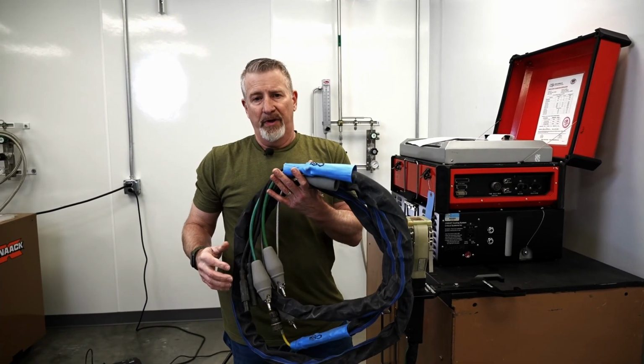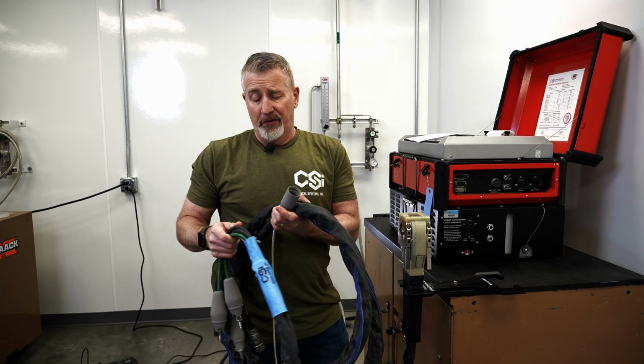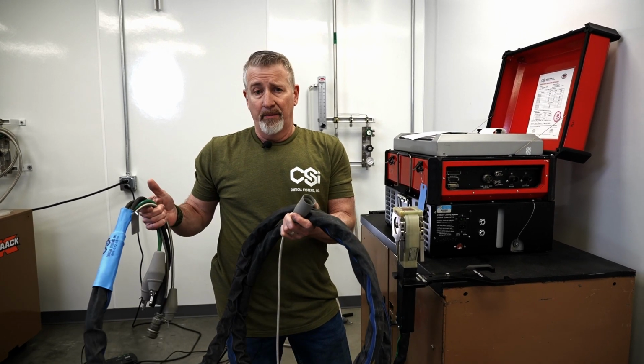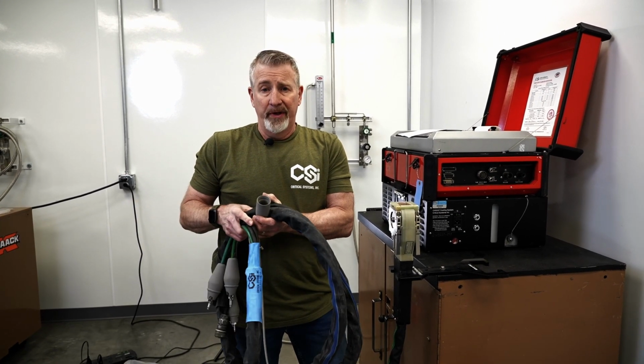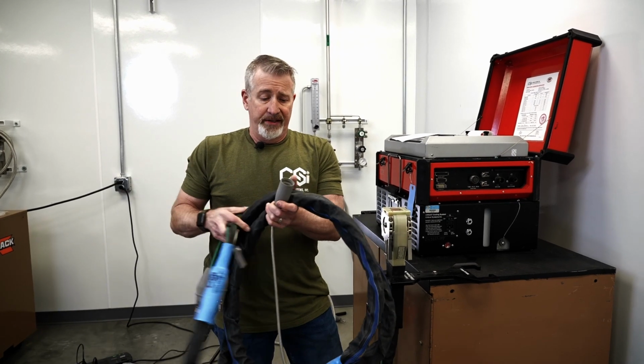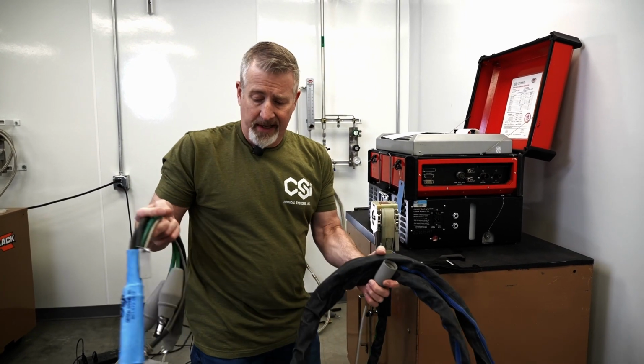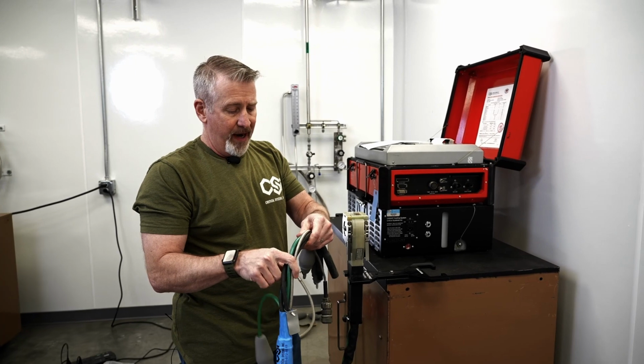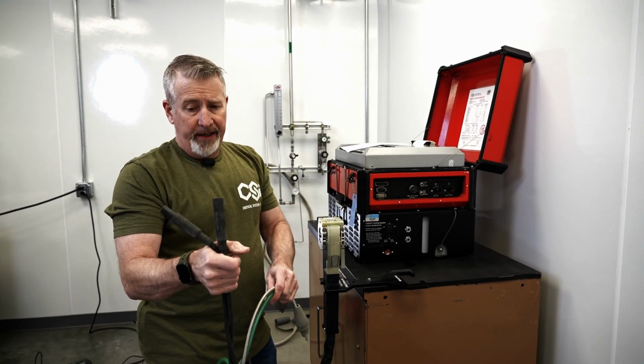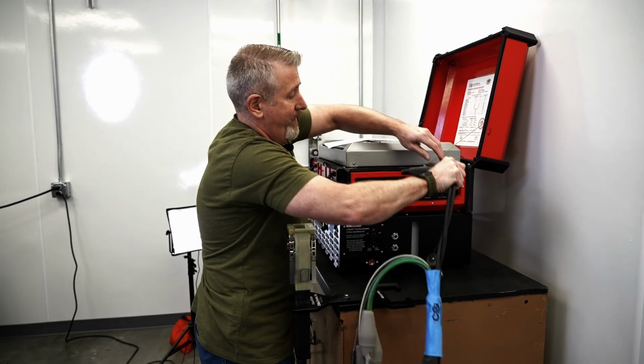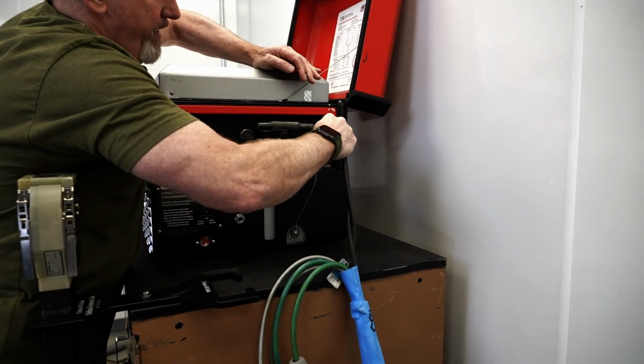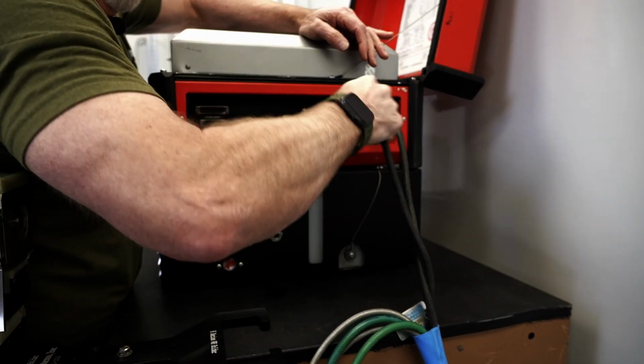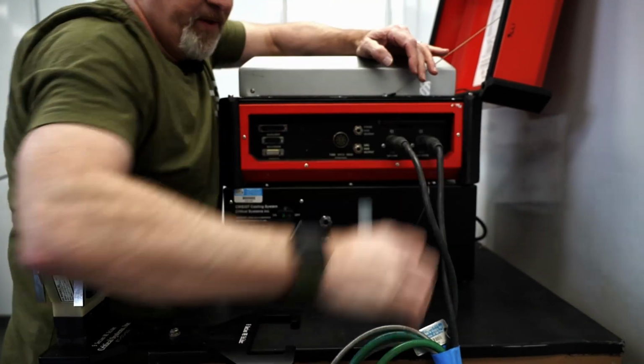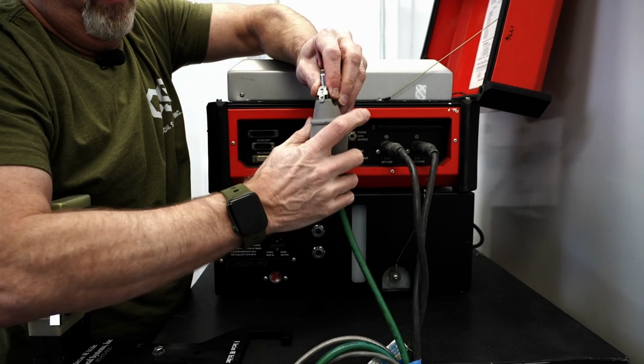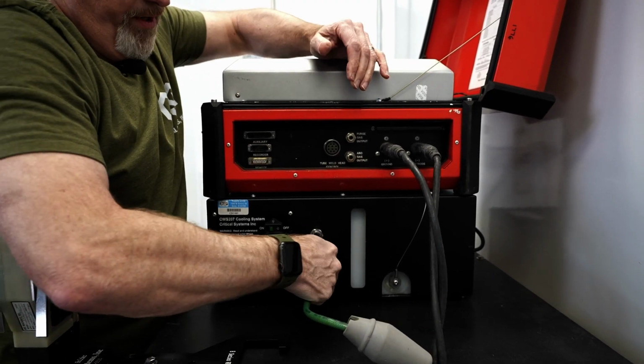This is a 15-foot adapter. It's just a longer version of the 1-foot adapter. If you need a little more distance, but you don't need 50 foot, you could use this. So it connects similarly to the 1-foot adapter. You have your cam lock connectors. They connect into the cam lock ports on the power supply. Give those a twist. Then again, you have your chiller connections. Those go onto your cooling unit.